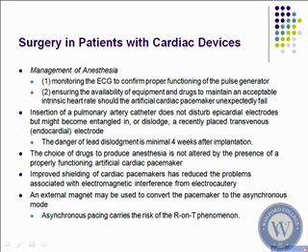Okay? If you have a bipolar, the distance is only between the two electrical poles, so it doesn't cause any disruption anywhere else. So you can be pretty close to the pacemaker with that kind of situation and not cause any problems. So if you do have to use the unipolar one, then you should try to put the grounding pad between the surgical site and the pacemaker. That's the preferred route. Okay, some people will put it away from it, but what they're actually telling us to do is put it in between. Some of the books will recommend it that way, which makes sense. I mean, the electrode, that way the current dissipates before it goes up.